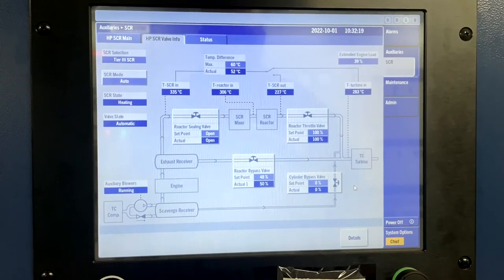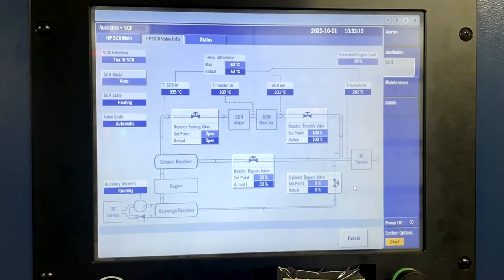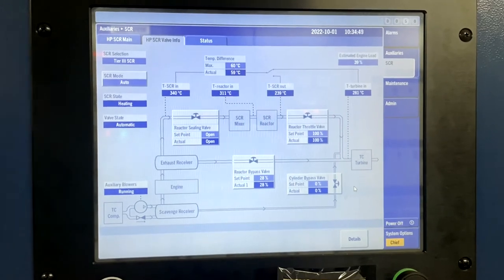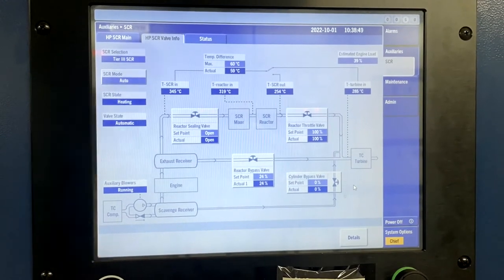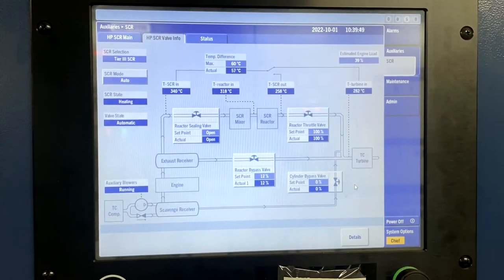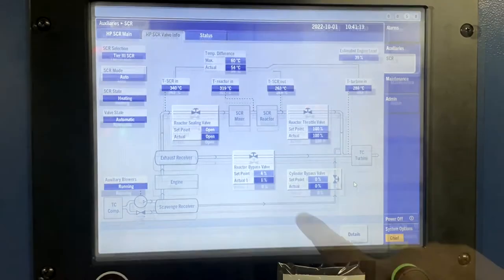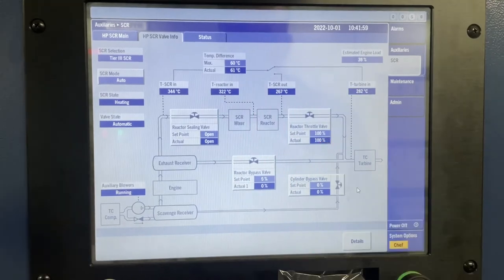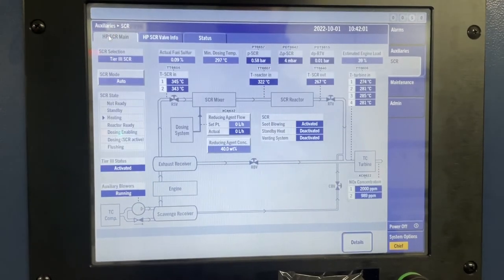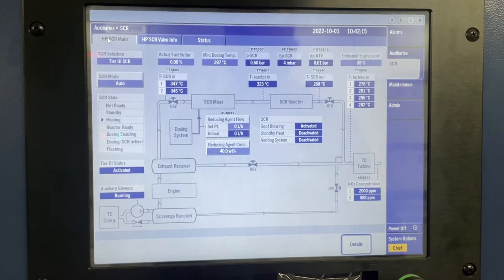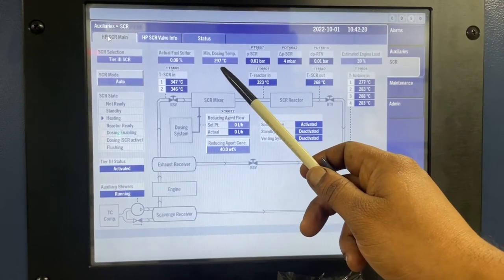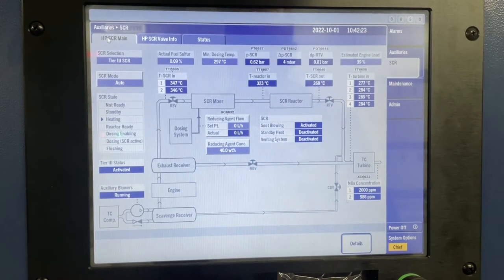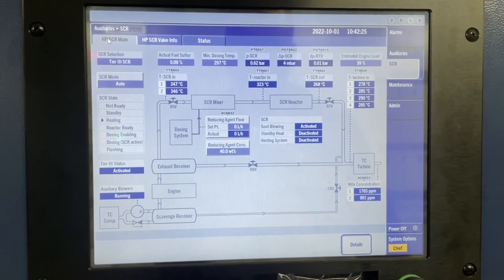You can see now RTV is fully opened. Now the RBV will start to close. Once the RBV is fully closed and RTV is fully opened, the heating continues to bring the reactor to the minimum dosing temperature for the SCR reactor. The minimum dosing temperature is 297°C, and this has to be reached at the SCR reactor outlet.